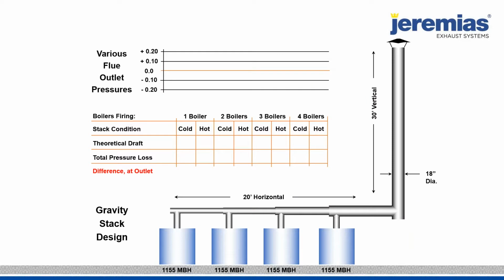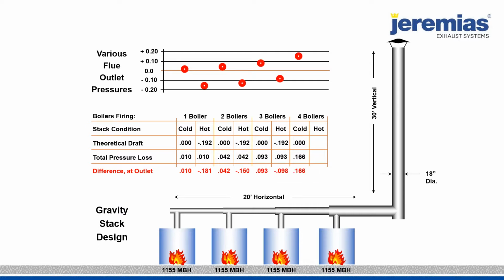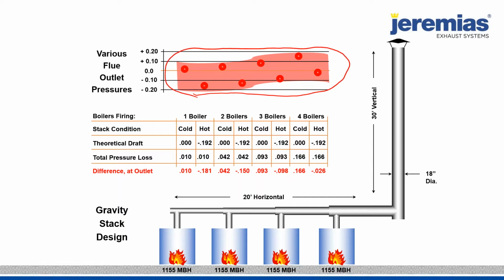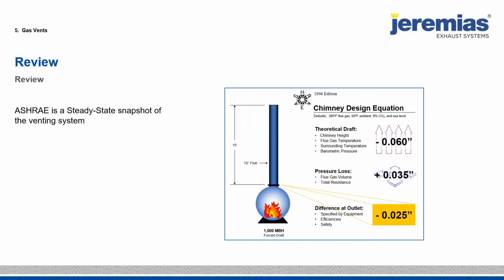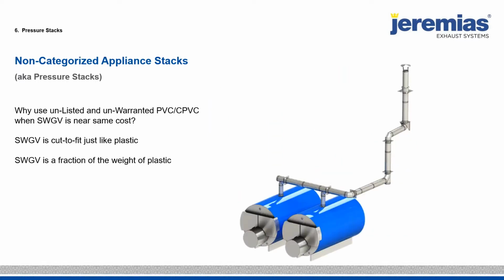Now, everything we looked at was a dedicated stack. So when we start combining appliances together, condensing or non-condensing, forced draft or condensing, we always got to make sure that the various pressure range is always acceptable by the appliance manufacturer. So no one knows more about all the appliances out there than Jeremias. We work closely with all the appliance manufacturers. So again, we can go in very much depth with this chimney design equation with your engineers at your office at any time.